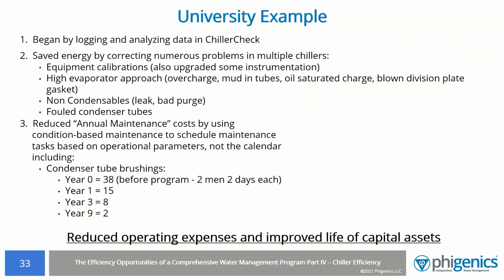This is an example of a university that had about 38 chillers. They had a lot of issues to begin with, a lot of water treatment issues, maintenance issues. We went through a whole series of processes to get everything running in the right direction and get them back online. And what we found out was after we implemented the processes, we used the program of logging and log analysis to determine if in fact there were issues that we needed to look at from a maintenance standpoint.